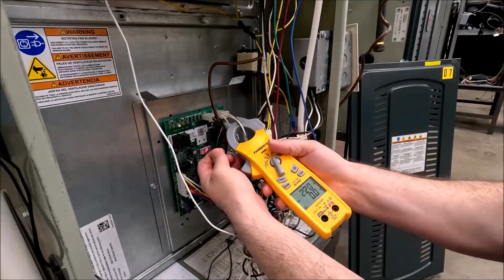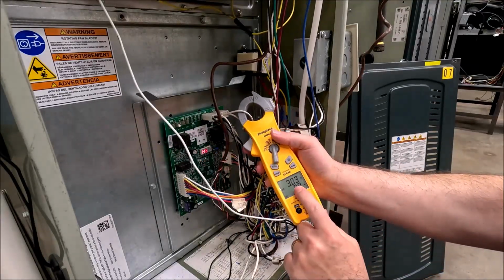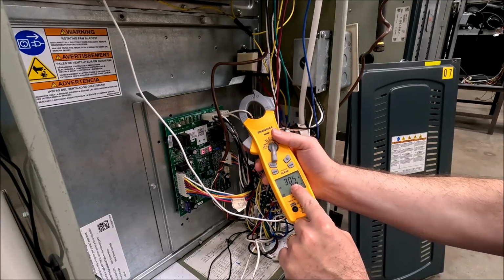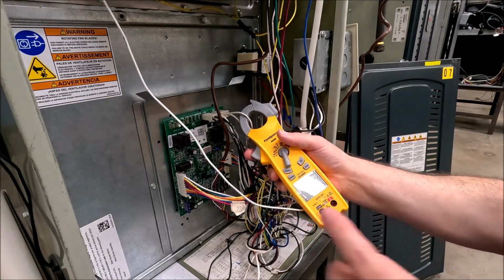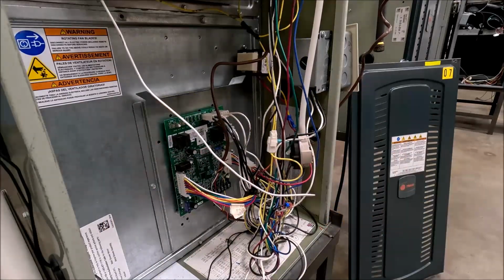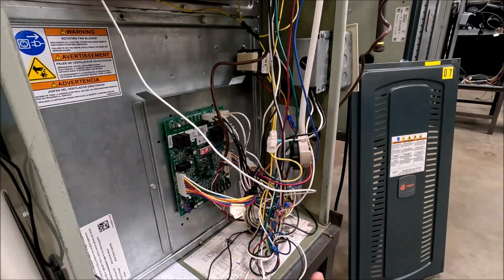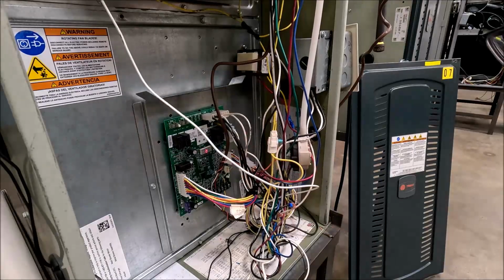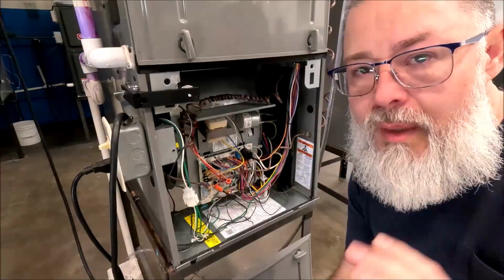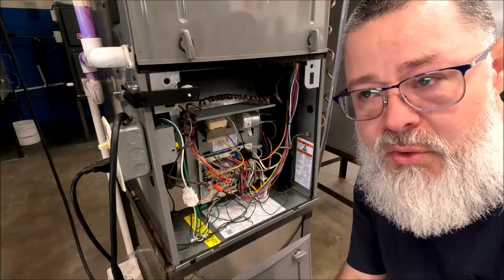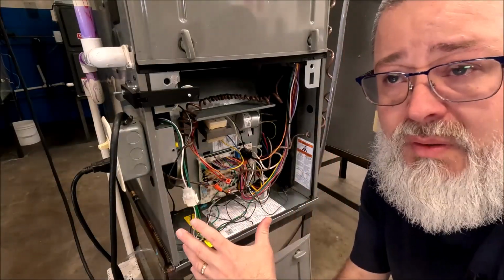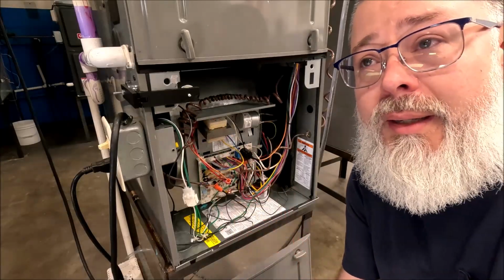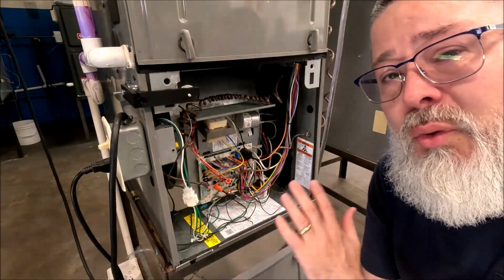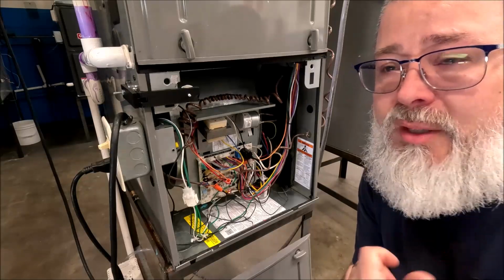And since it's 120 volts, I always check the neutral, and you can see here we're looking at about 3 amps for that X13 motor that's behind this cover. So even though you can't see it, I know it's working. I can feel airflow in the return and the supply side, but it's the neutral. Now on this furnace, I've got a 120 volt setup, split system style furnace that we've got a heat pump on actually. So this will be a dual fuel unit, but we're looking specifically at this blower motor.